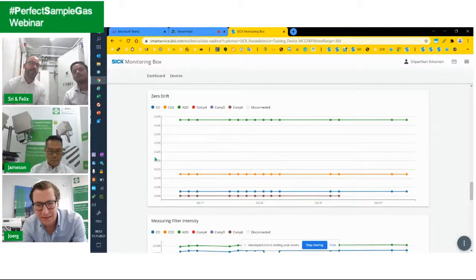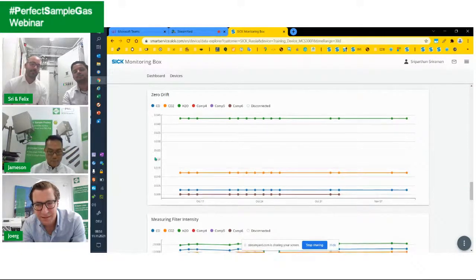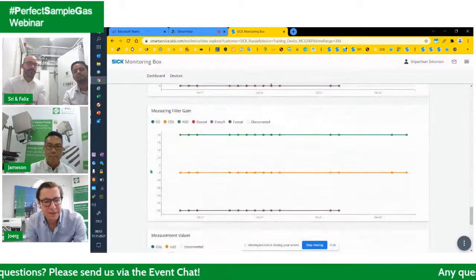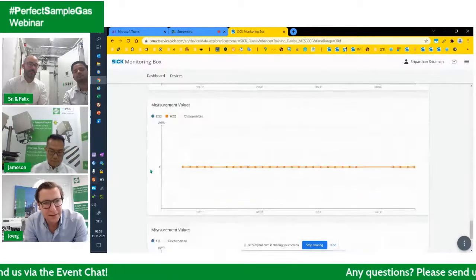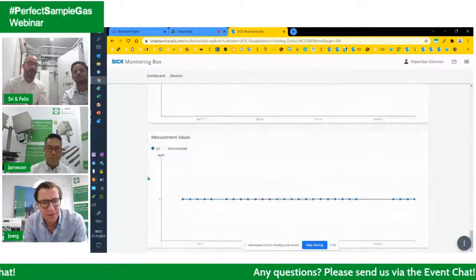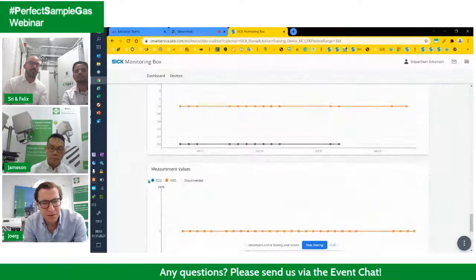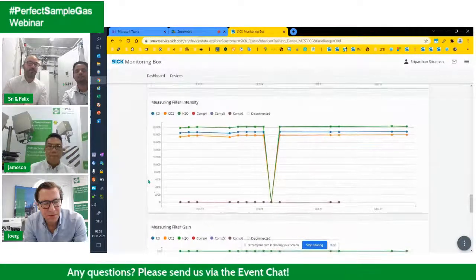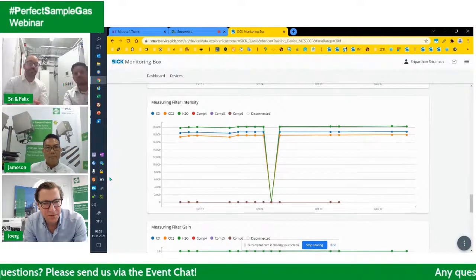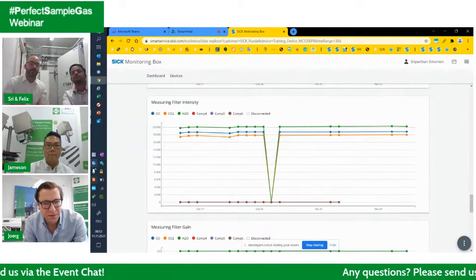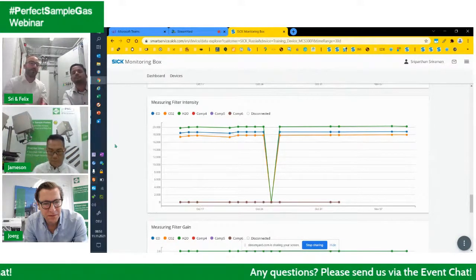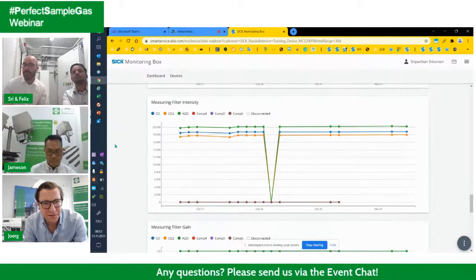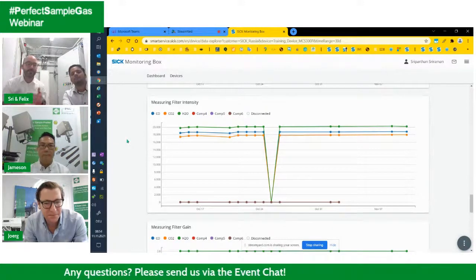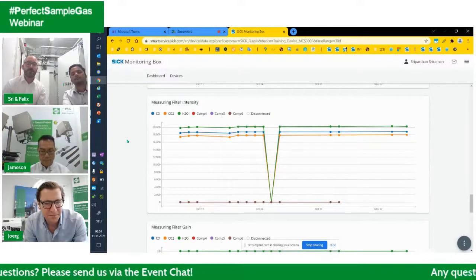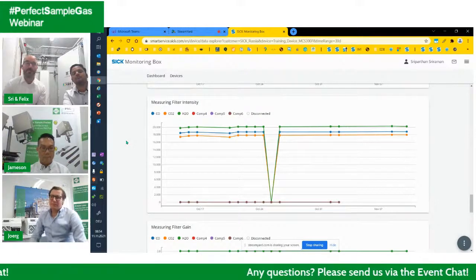And as all SICK analyzers are connected to the same systems, if a gas analyzer is telling the operator 'I need maintenance, please order a particular spare part,' the other analyzers within this network can also say, 'okay, if a SICK engineer is coming on site anyway, please do the quarterly maintenance on the following analyzers as well.' So we can save time, save money, be more efficient, and increase the overall system uptime of all the systems within this network.